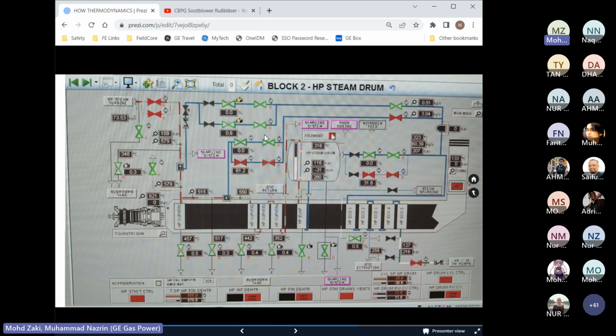Spray water's function is to control the superheater temperature. We have a limit on the temperature, so we don't want the temperature at this stage to go up too much. So we give spray water to reduce back the temperature. Then it goes to the final stage of the HP superheater tube, and the temperature will move up to almost 600 degrees C.